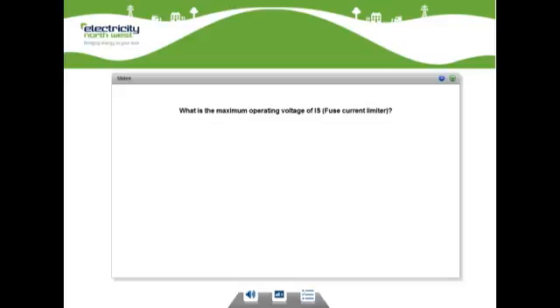The next question is, what is the maximum operating voltage of the IS fuse current limiter? We're really looking at an 11 kV solution for the Respond project. I'd have to refer back to ABB to find out exactly what the maximum voltage would be, but I would suggest it's somewhere in the sort of 20 kilovolt range. Yeah, again, the details we're aware of is what we're using in this site, which will be two primary substation sites. We would, again, refer back to ABB whether they provide IS limiters for higher network voltages.